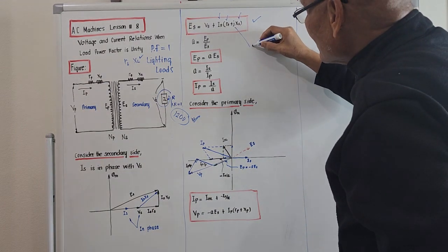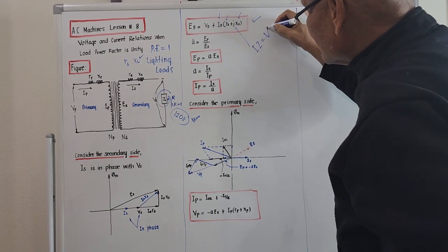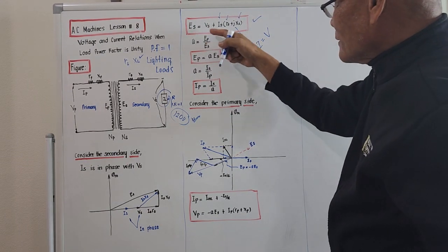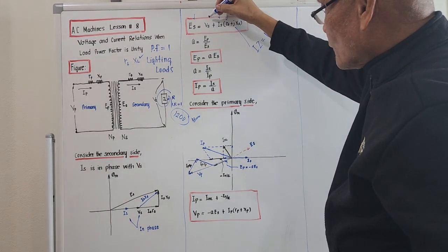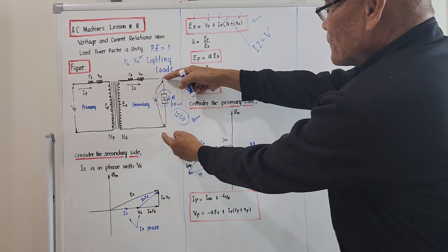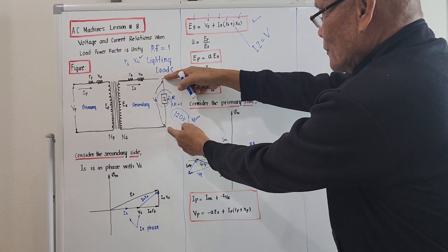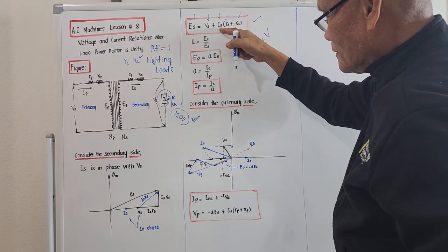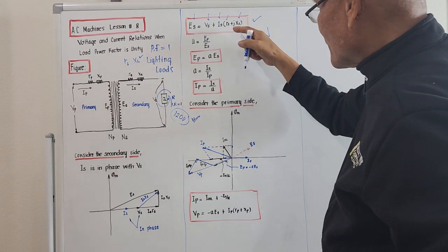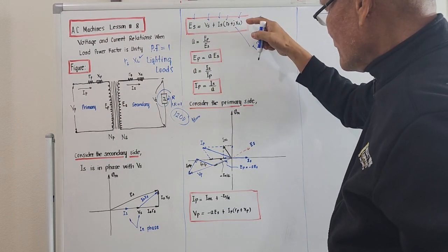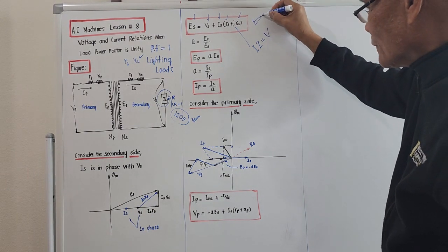How is that so? Because the product of current times impedance is equal to voltage. So actually we are taking the summation of voltages here. That is, the induced voltage will be equal to the value of Vs, the one that appears at the terminal going to our service entrance, plus the product of the current that will be coming out due to this load, times the vectorial sum of RS plus JX of S. So this is actually the relation.